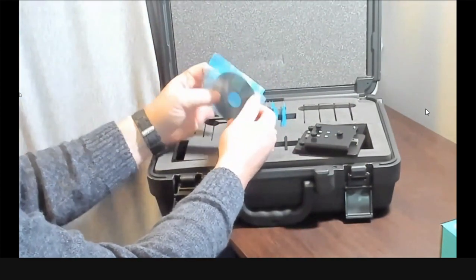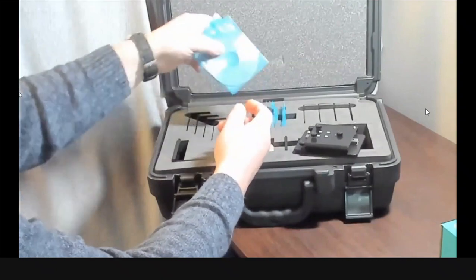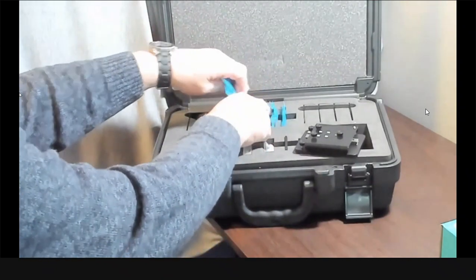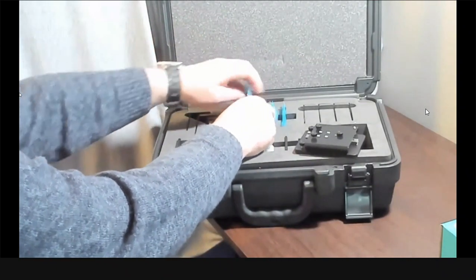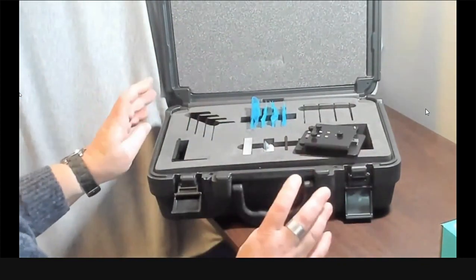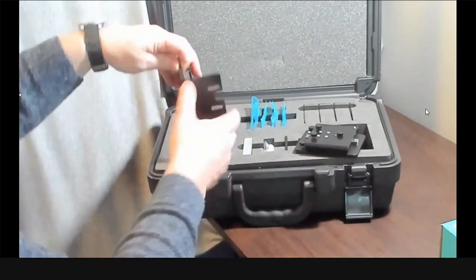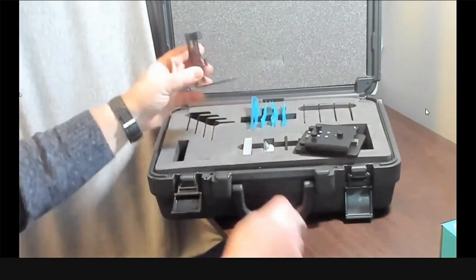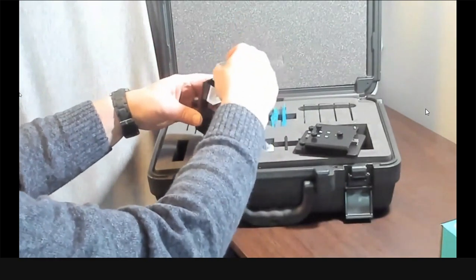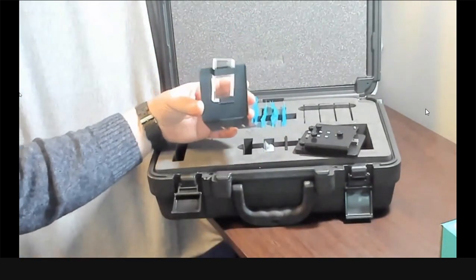These are the aperture plates. You will notice the aperture plate has a white surrounding. If you're going to do a transmission measurement, make sure the aperture plate has a white ring near the sphere to cover the whole sphere. That's why it has an additional white ring.